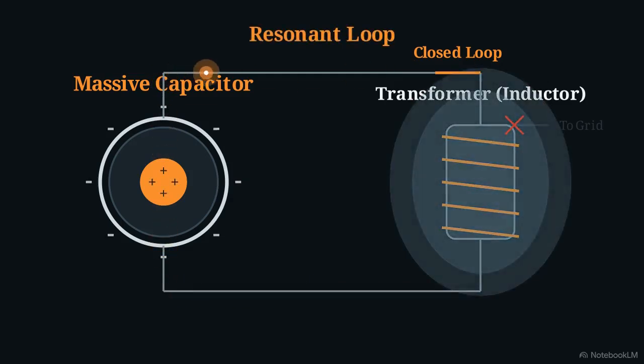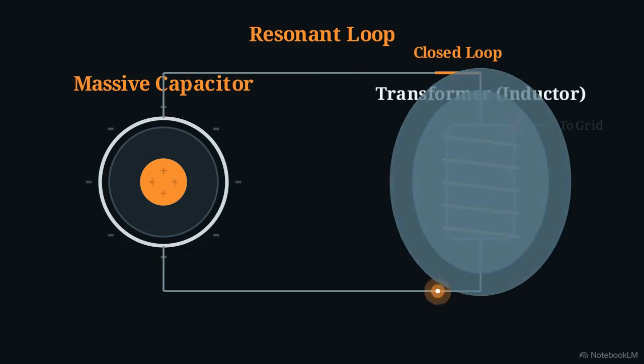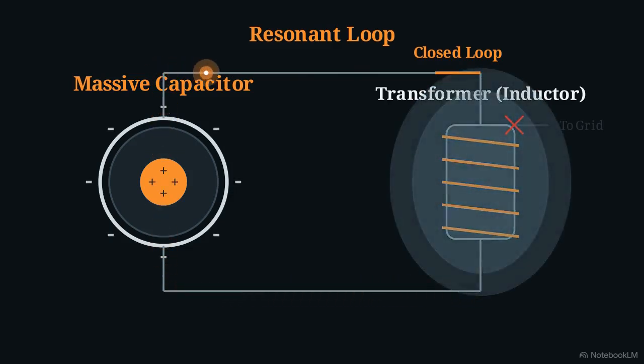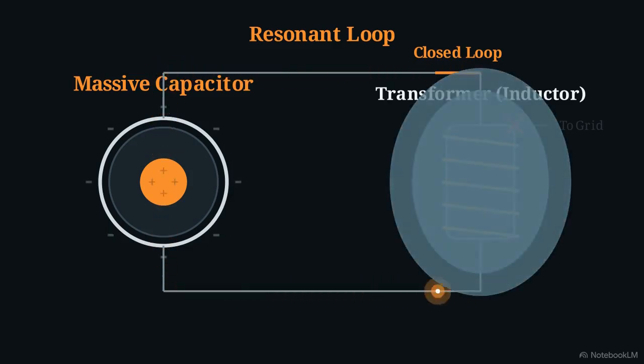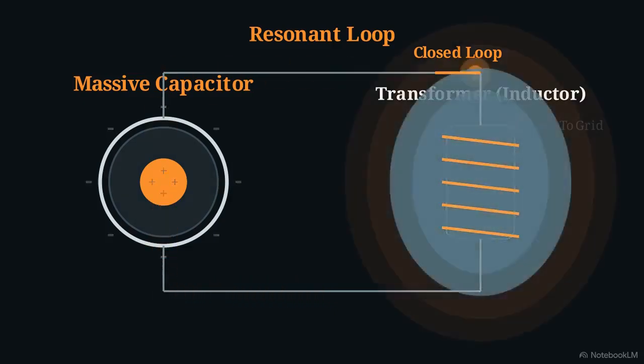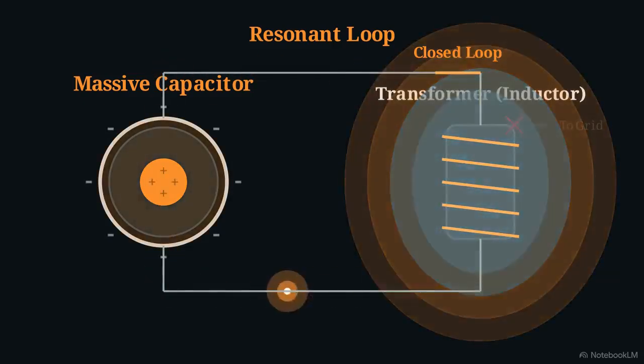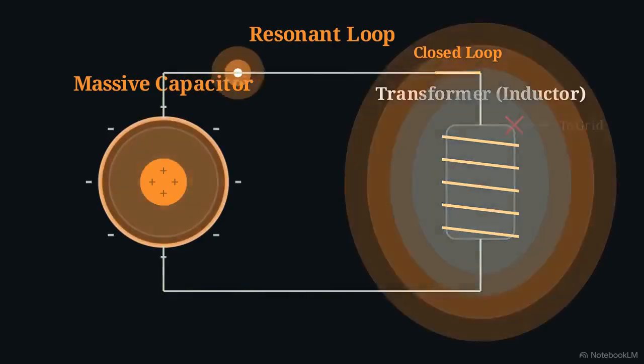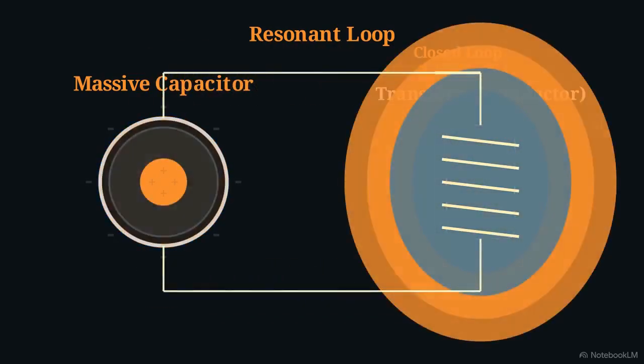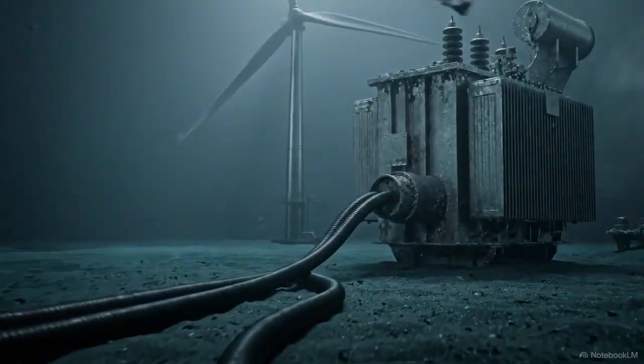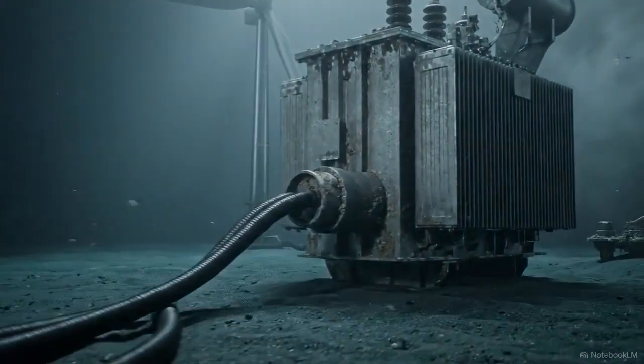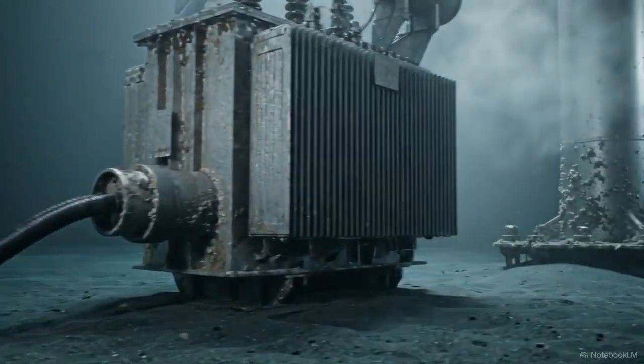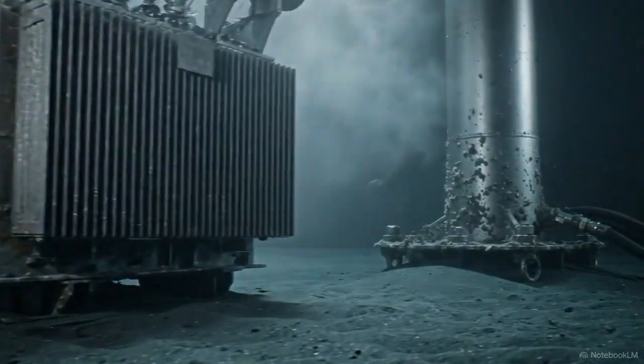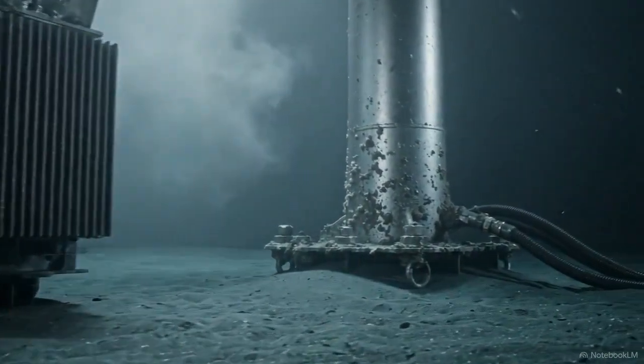Unable to escape to the grid, the trapped electrical charge and magnetic energy violently pass back and forth between the cable and the transformer. This creates a self-sustaining resonant loop. The energy bounces rapidly, compounding in intensity with every single cycle. The necessary physical architecture of an offshore wind farm, miles of cable wired to heavy transformers, inherently provides perfect ingredients to build this self-sustaining energy snare.